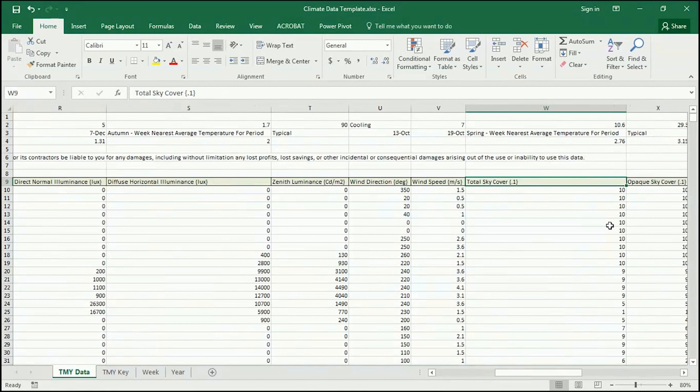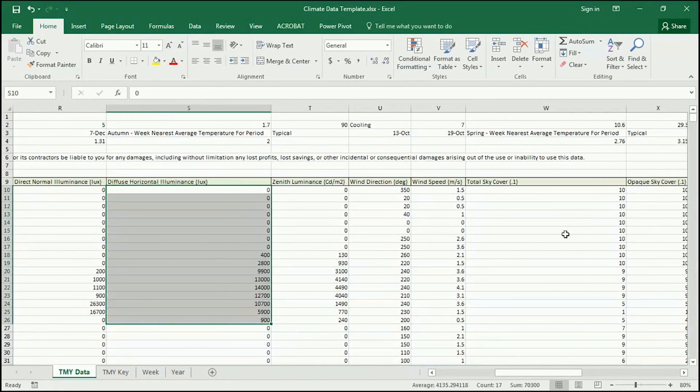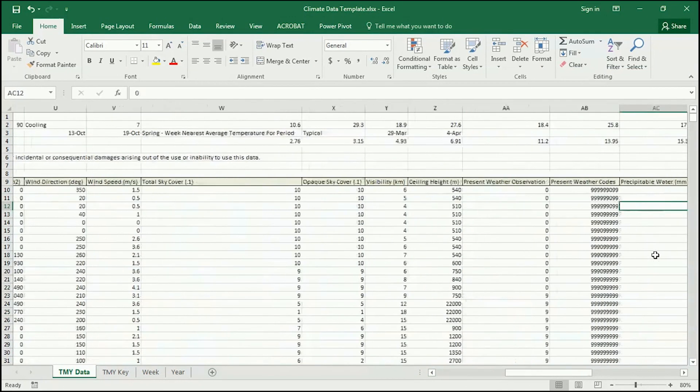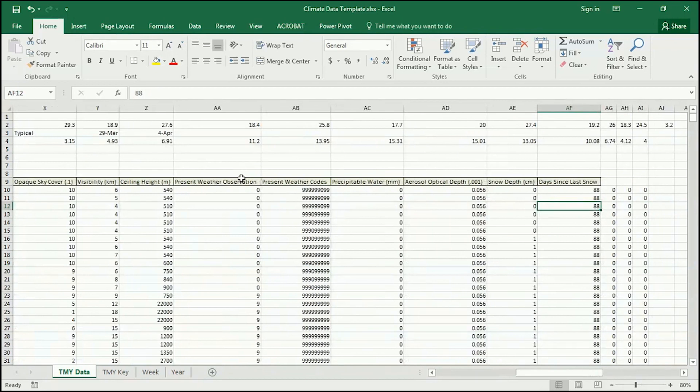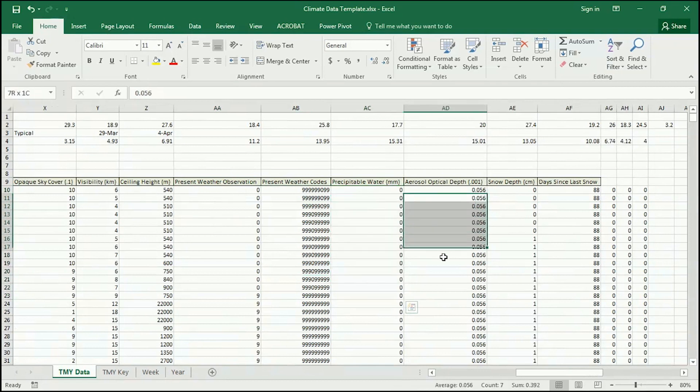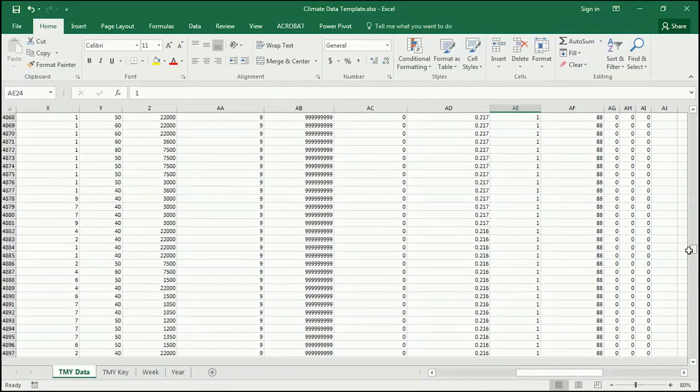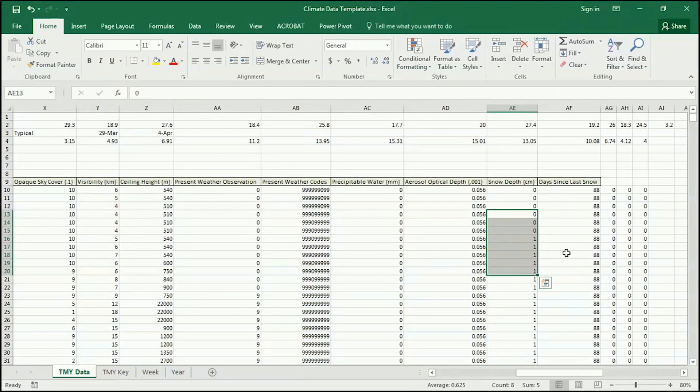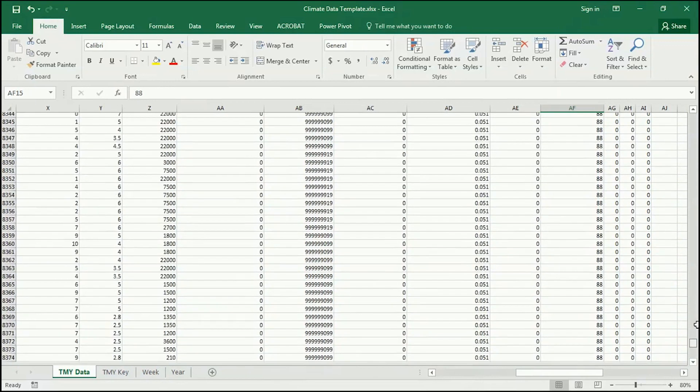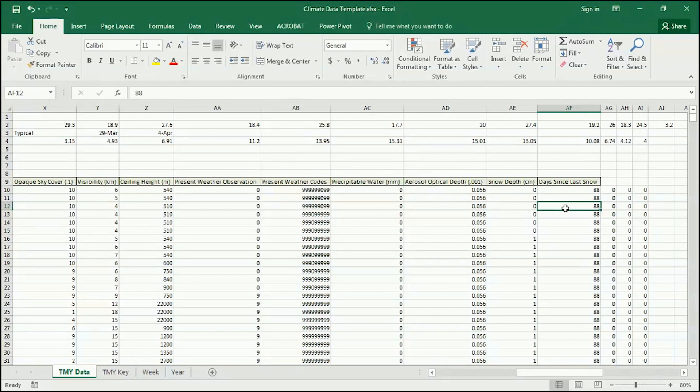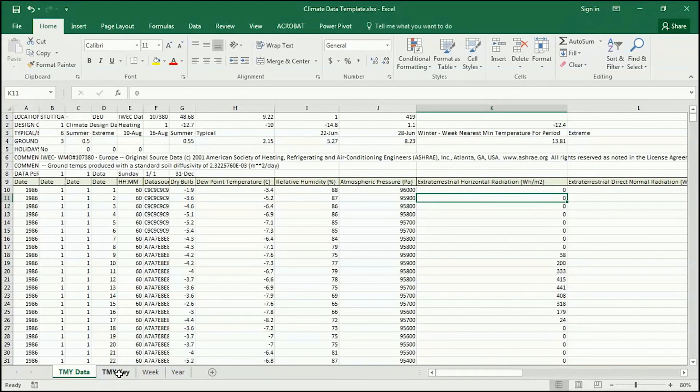One thing to do is to scan the data and make sure that there's nothing, no bad data. You can see that this goes from 0 to 400 to 2,800, et cetera. So this looks like good data. If we go to the right here, you'll see that there's a few columns that probably have zeros in them. The present weather observation is all zeros. The weather codes are nonsense. The precipitation is all zeros. The aerosol optical depth is all the same number. The snow depth actually looks like, in this case, it is collecting some data, which is unusual. I almost never see that. I don't know how reliable that data is. And then days since last snow is also not, it's all 88s there. So it's important to check the veracity, the truthfulness of the data to make sure that you're looking at things that are reasonable. So this looks good.